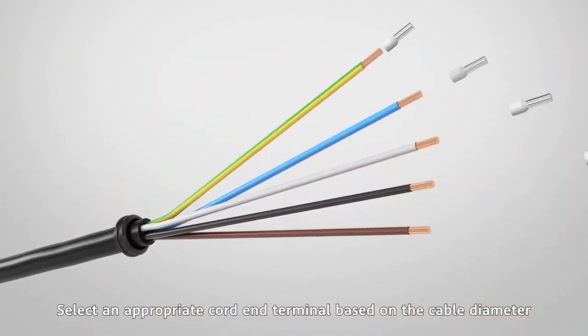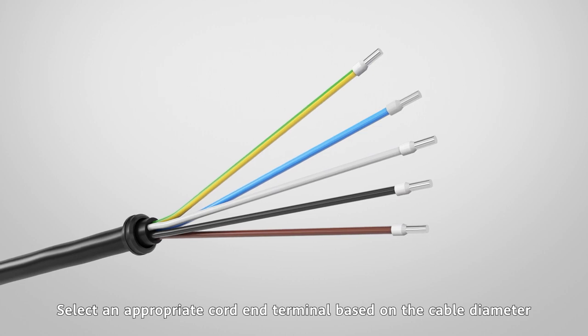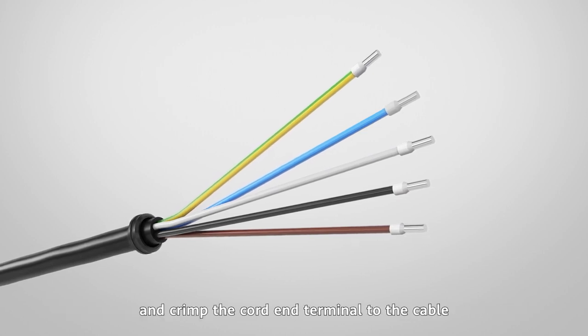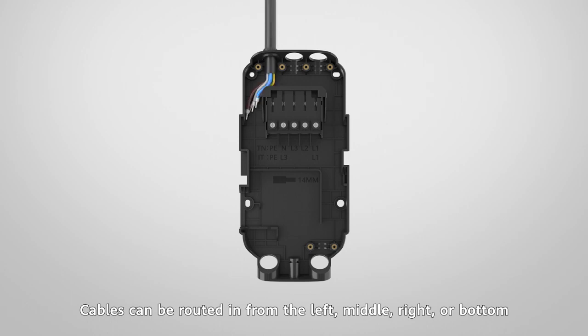Select an appropriate cord end terminal based on the cable diameter and crimp the cord end terminal to the cable. Cables can be routed in from the left, middle, right, or bottom.